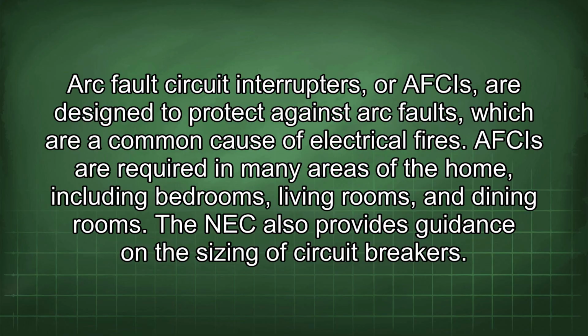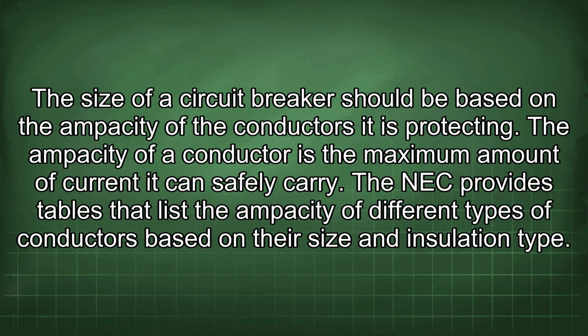The NEC also provides guidance on the sizing of circuit breakers. The size of a circuit breaker should be based on the ampacity of the conductors it is protecting. The ampacity of a conductor is the maximum amount of current it can safely carry. The NEC provides tables that list the ampacity of different types of conductors based on their size and insulation type.